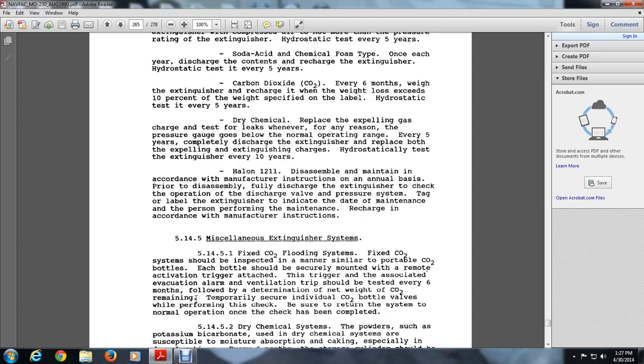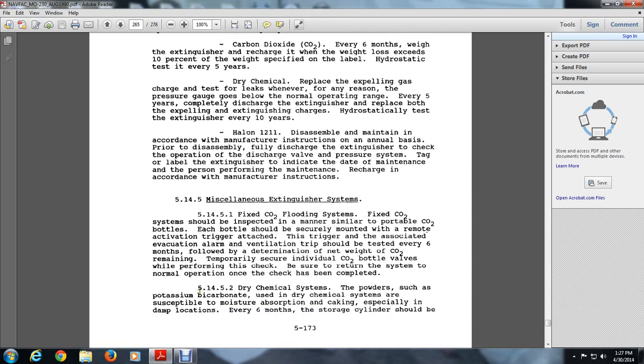The trigger associated with the evacuation alarm and ventilation trip should be tested every 6 months, following determination of the net weight of the carbon dioxide remaining. Temporarily and securely, individual carbon dioxide bottle valves will primarily be checked, and be sure to return the valve system to normal operation once the check has been completed.